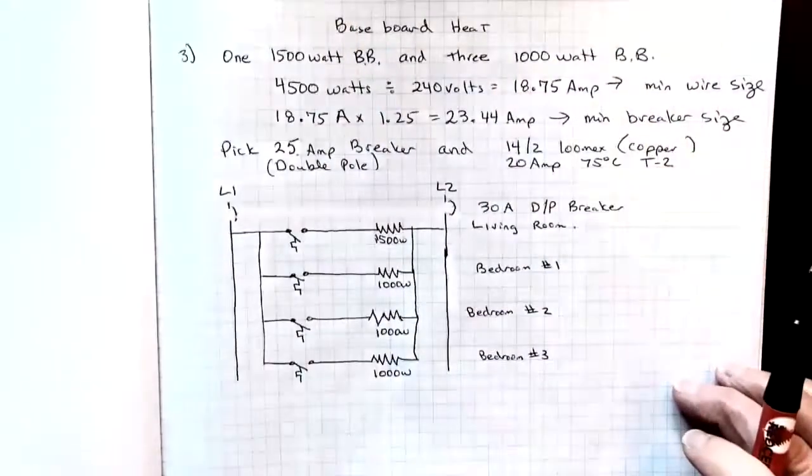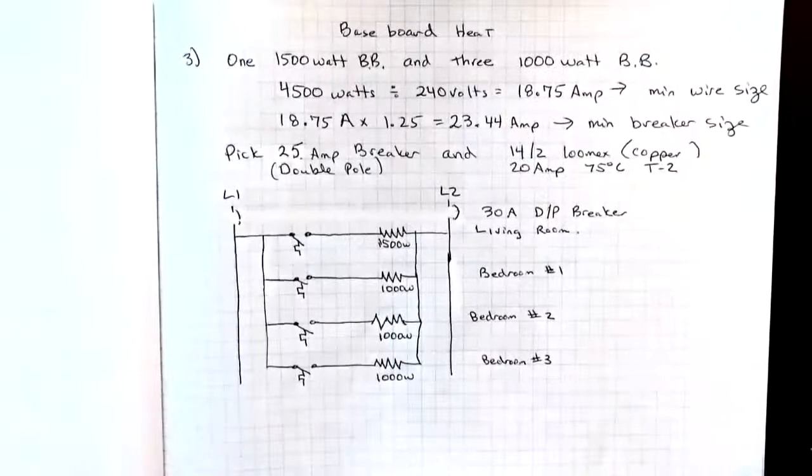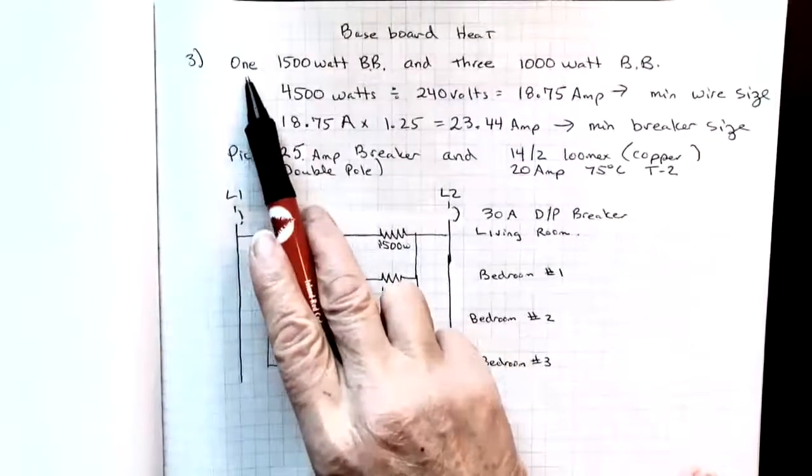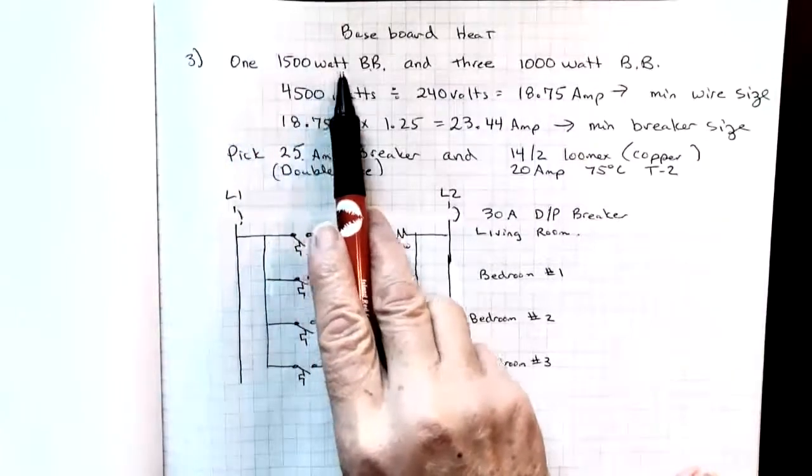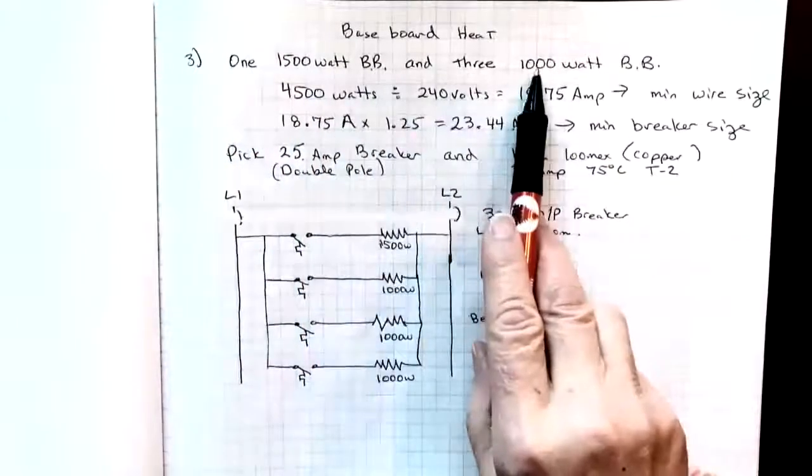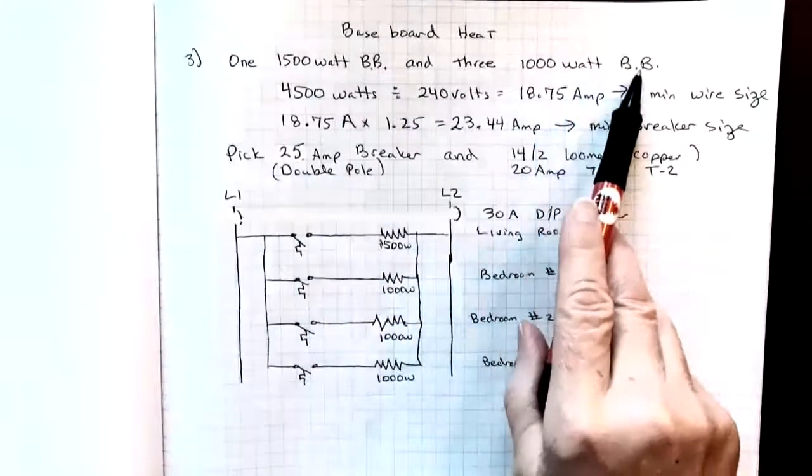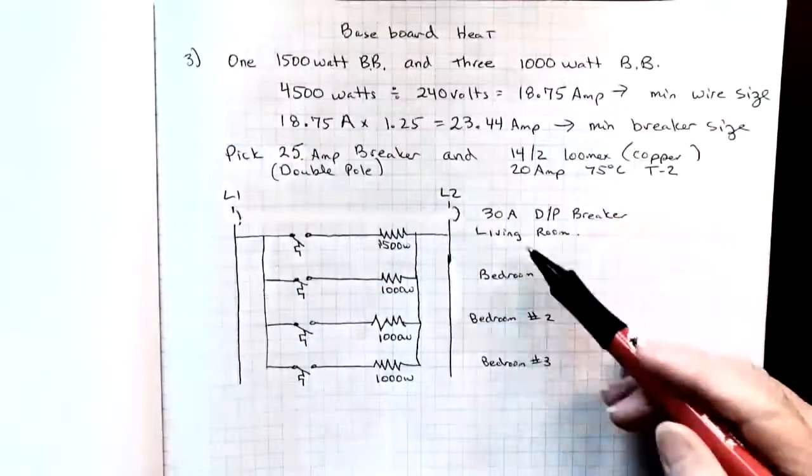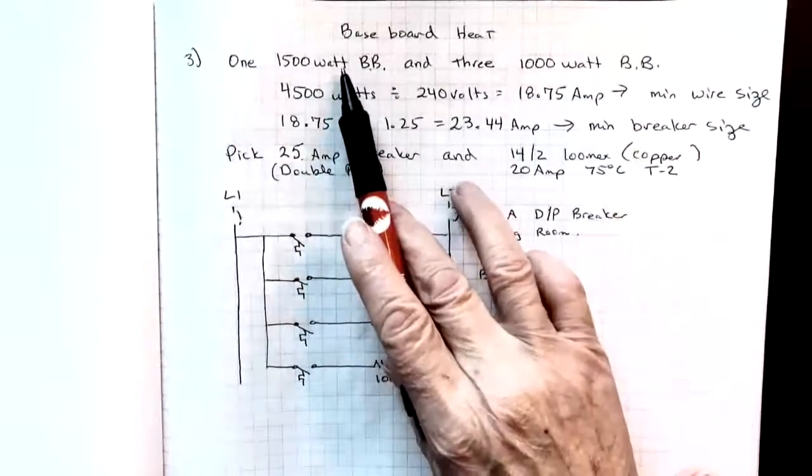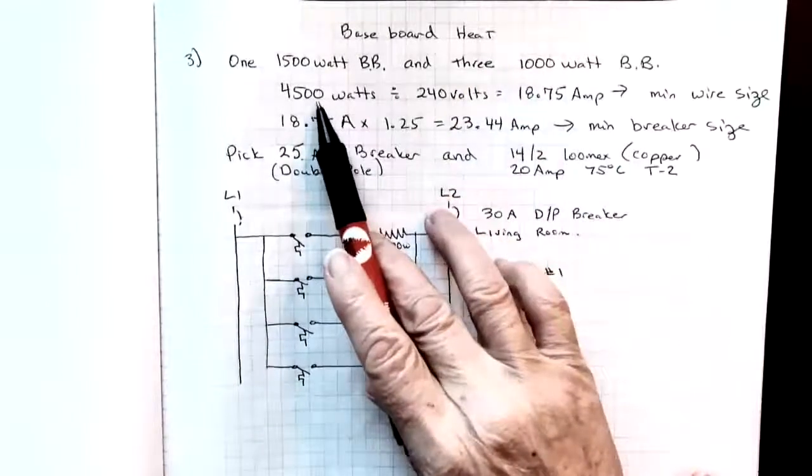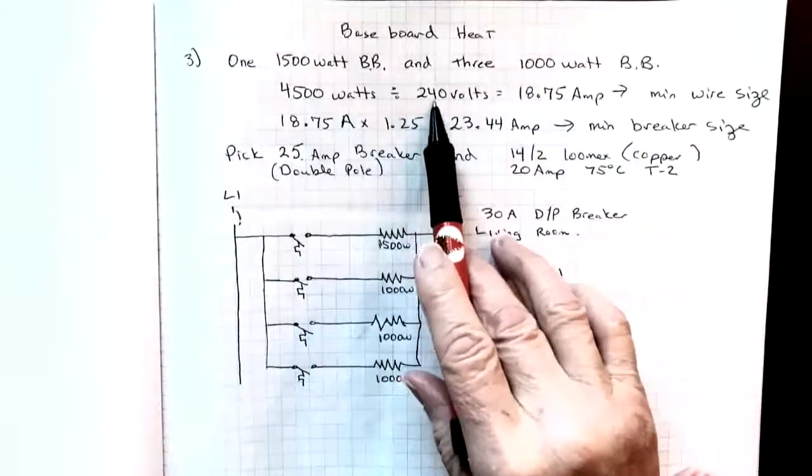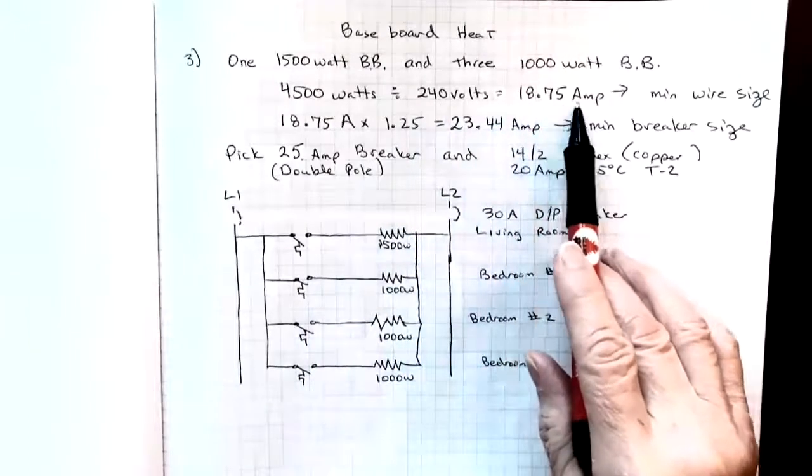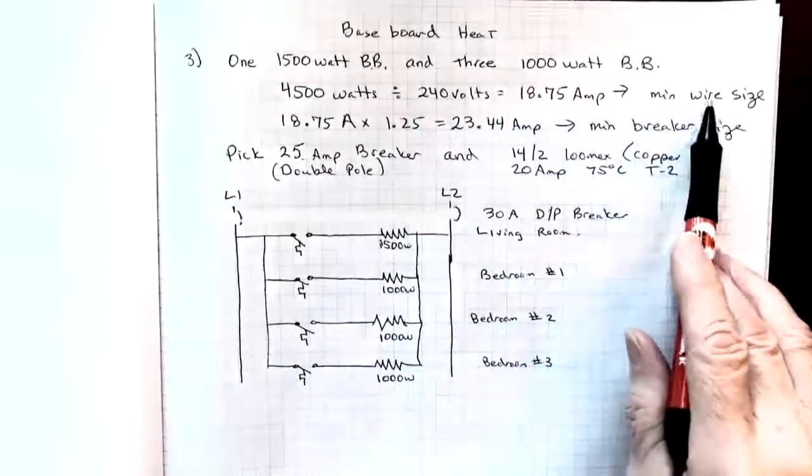Often we load up our baseboard heater circuits. And in this case, my third example has one 1500 watt baseboard heater and three 1000 watt baseboard heaters. For example, this might be one in the living room, one in each of three bedrooms. So add up those wattages, I get 4500 watts, assuming it's 240 volts divided by 240 gives me 18.75 amps. That's my minimum wire size.